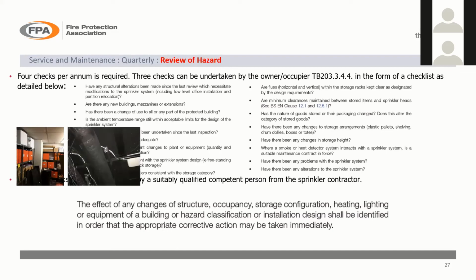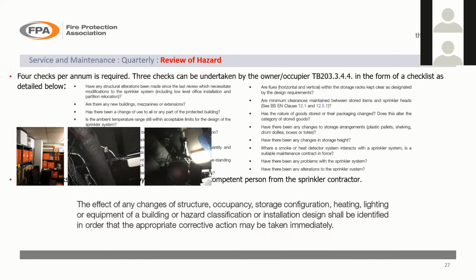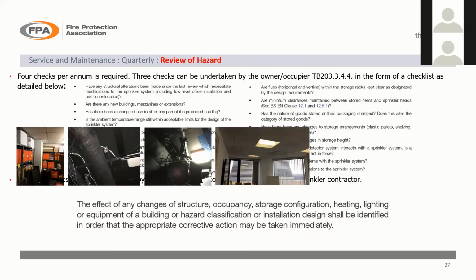We saw sprinklers where services are being put beneath the sprinklers installed, so it's obstructed them. This picture is a room which once was an office, it's been converted into a TV studio, so you've got lots of electrics and other things in there now. It was never designed as a TV studio, so it's an ordinary hazard Group 3 system, which really should be an ordinary hazard Group 4 system now, bearing in mind it's got lots of electrical cables, TV sets, lots of combustible materials. And just by chance in that particular building, lots of combustibles stored in there as well. So obviously, things like that would be flagged up on a review of hazard.